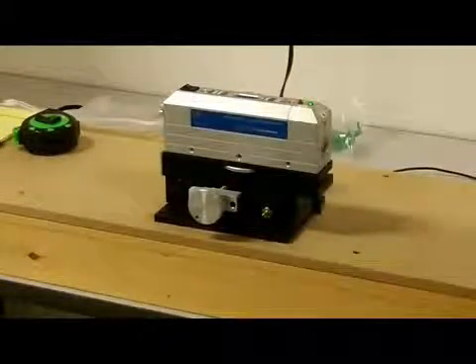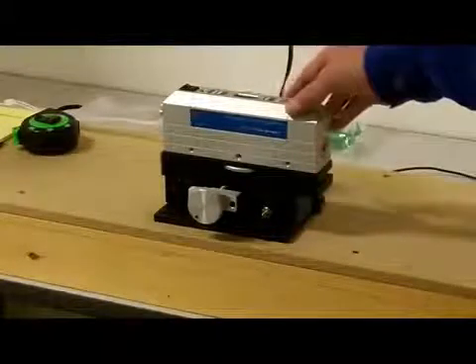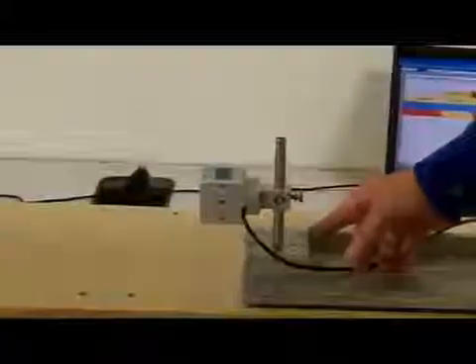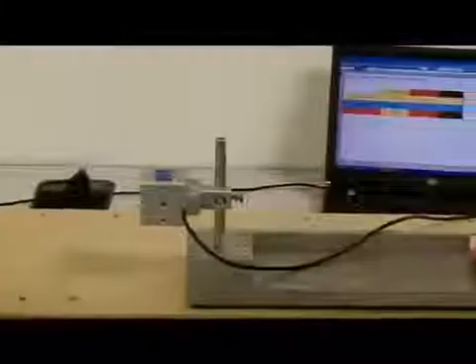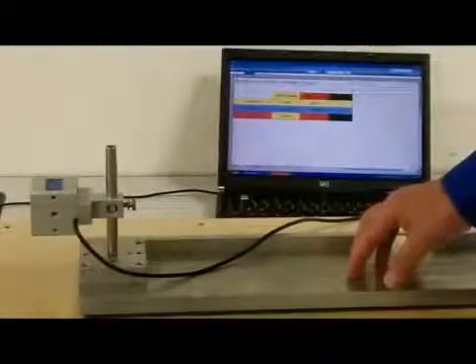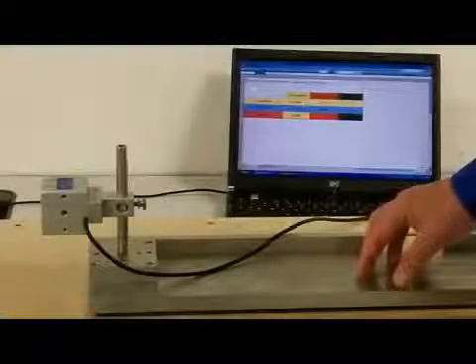The products we'll be using today to demonstrate the bucking in process are the Micro Gauge 2D laser, the four axis precision mount, and then we have our 2D receiver set up on our standard mounting block, which I'll move along this surface here to check. I'll be able to check the straightness of this rail and also the flatness of this plate. That is the benefit of the 2D system - it allows me to check both axes at the same time.